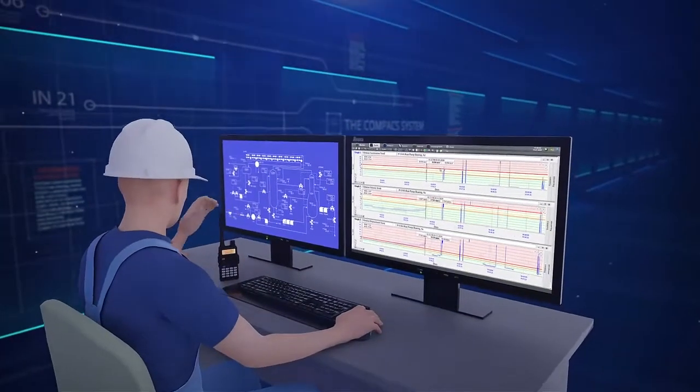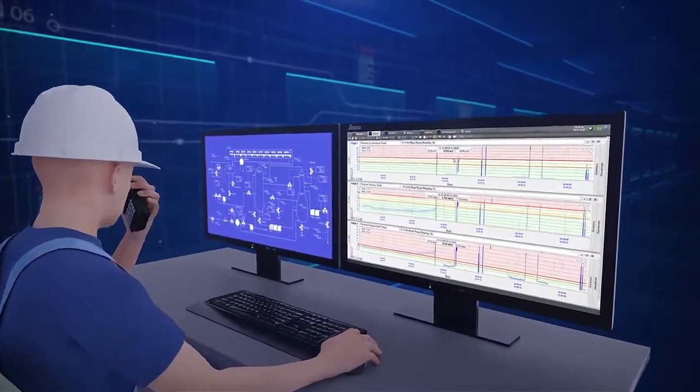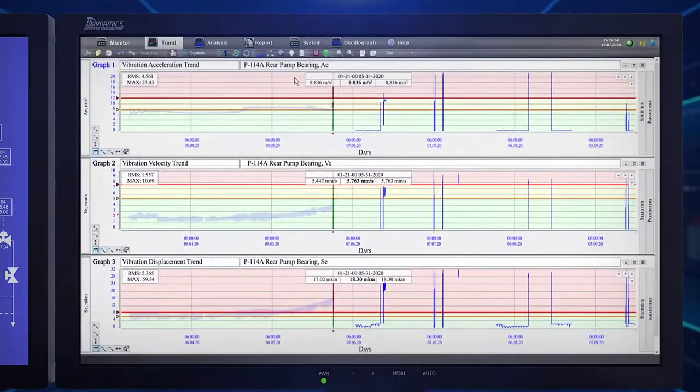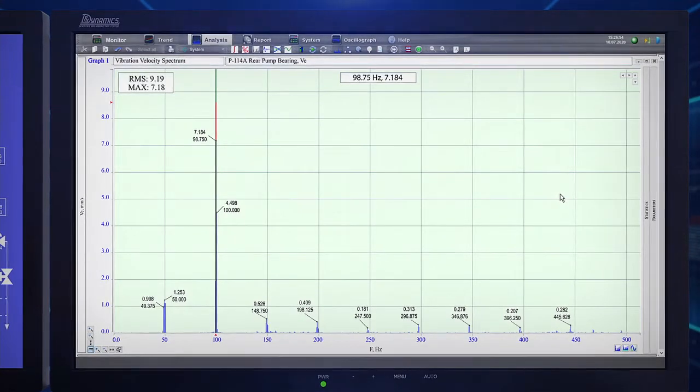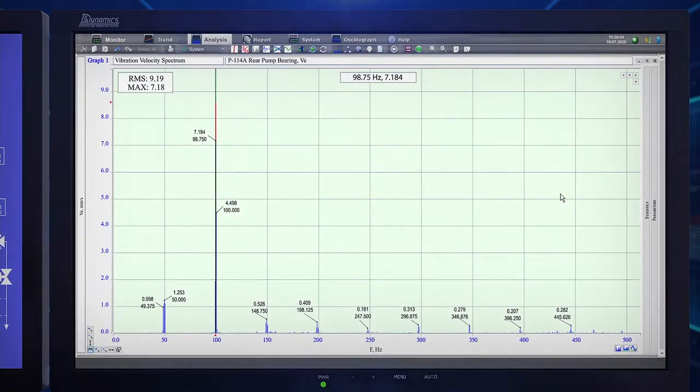To clarify the system's recommendations, the staff looked at the analysis screen. It's pretty clear that the vibration velocity and displacement spectra has a large peak at the 2x frequency. This is indicative of misalignment.